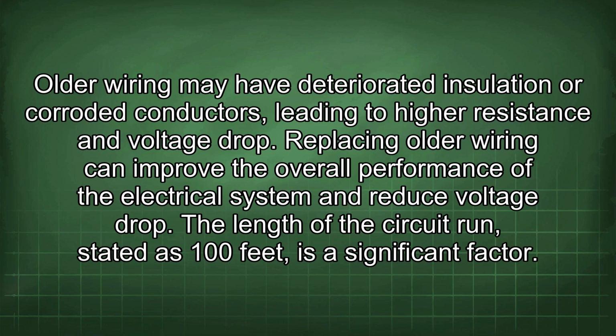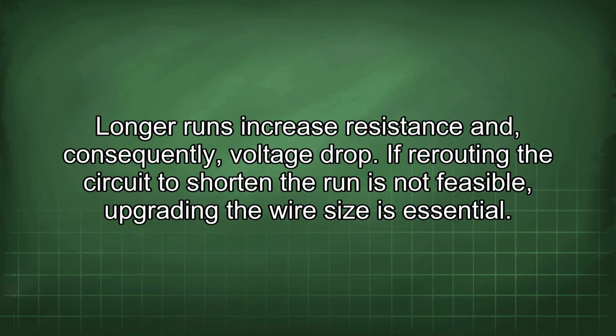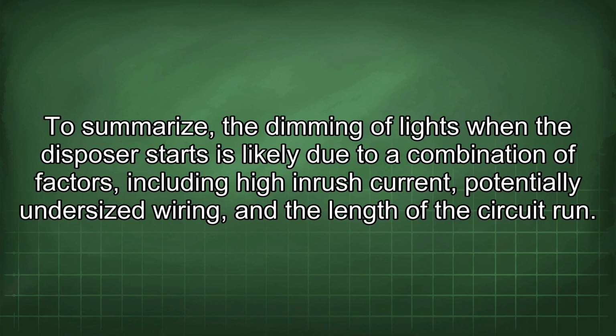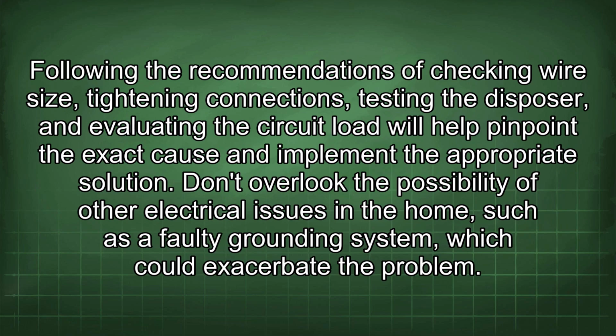The length of the circuit run, stated as 100 feet, is a significant factor. Longer runs increase resistance and, consequently, voltage drop. If rerouting the circuit to shorten the run is not feasible, upgrading the wire size is essential. To summarize, the dimming of lights when the disposer starts is likely due to a combination of factors, including high inrush current, potentially undersized wiring, and the length of the circuit run. Following the recommendations of checking wire size, tightening connections, testing the disposer, and evaluating the circuit load will help pinpoint the exact cause and implement the appropriate solution.